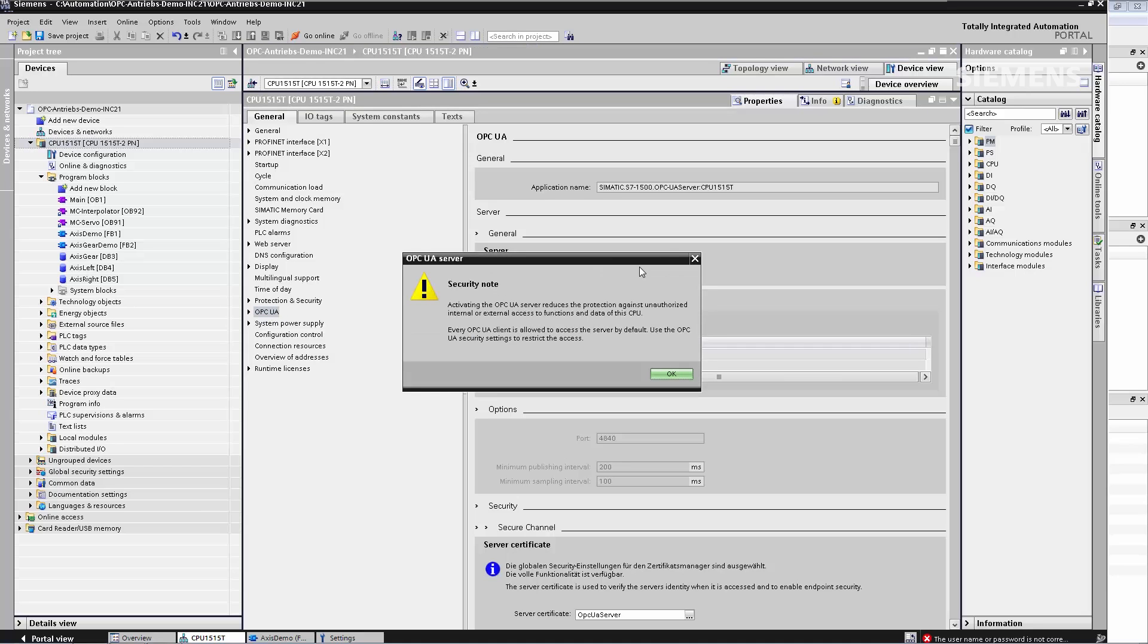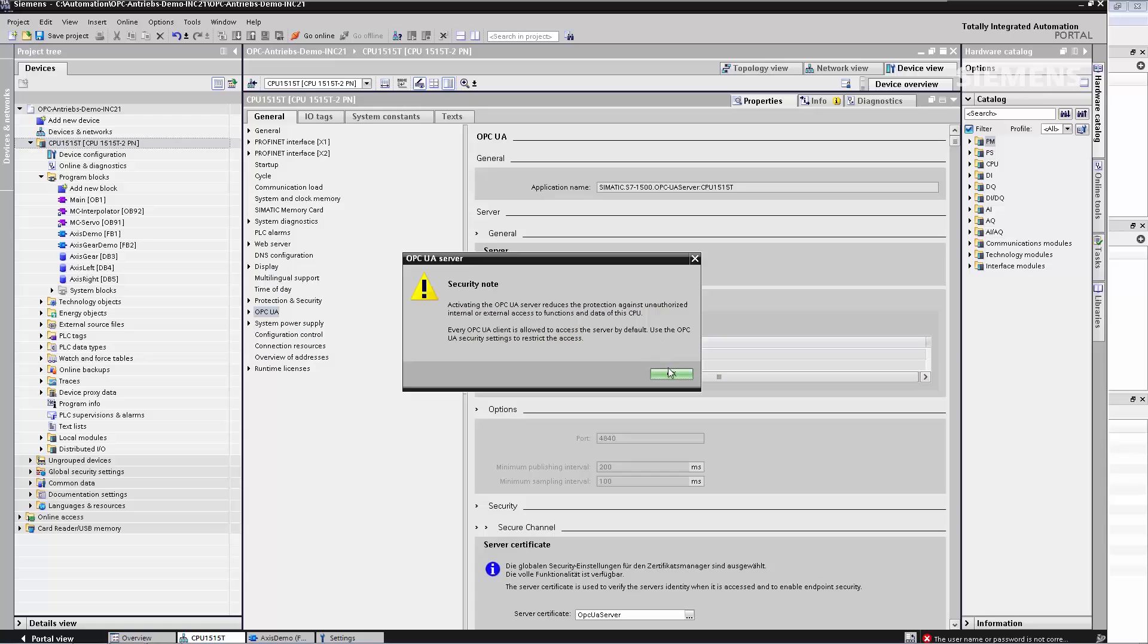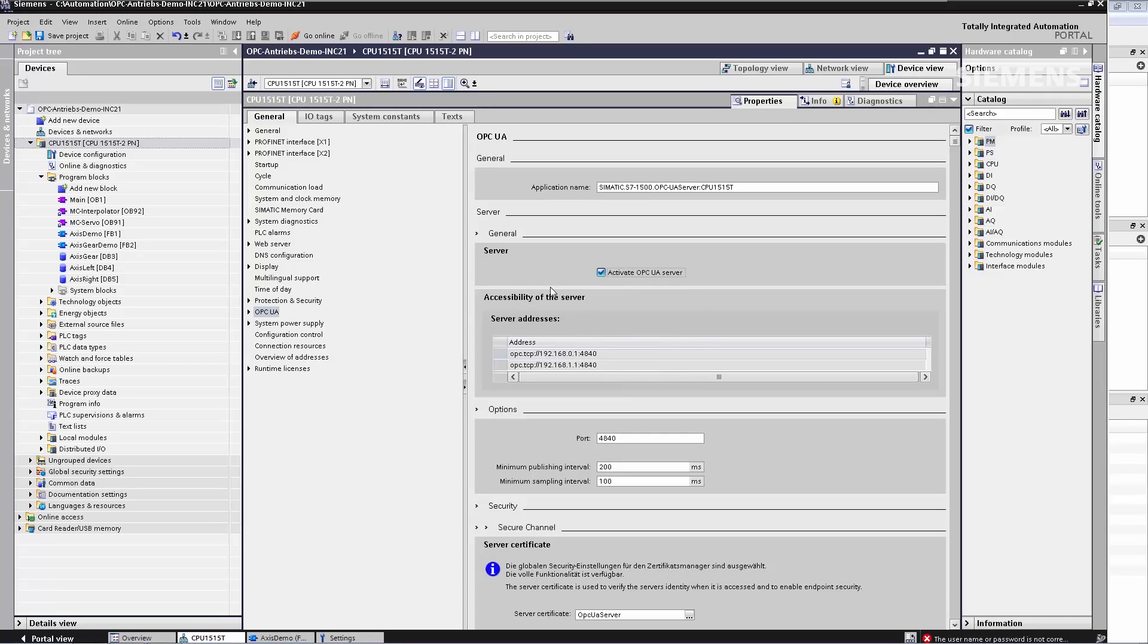I still have to confirm the pop-up security note. This informs me that, on one hand, I am opening an additional port for OPC UA. And on the other hand, that in the standard configuration, every OPC UA client is now allowed to access the CPU. I click on OK and step one is complete.